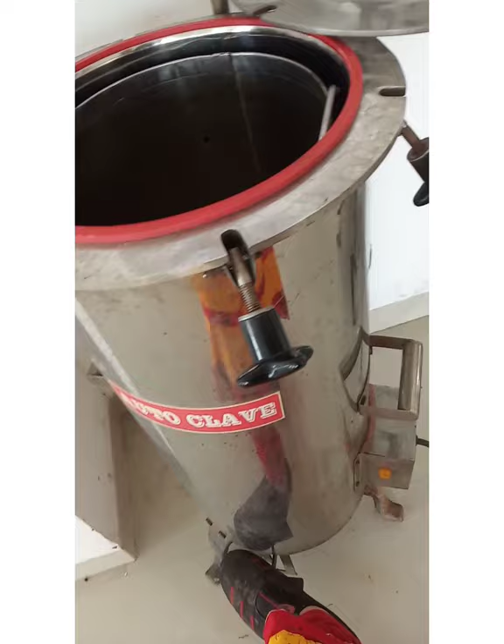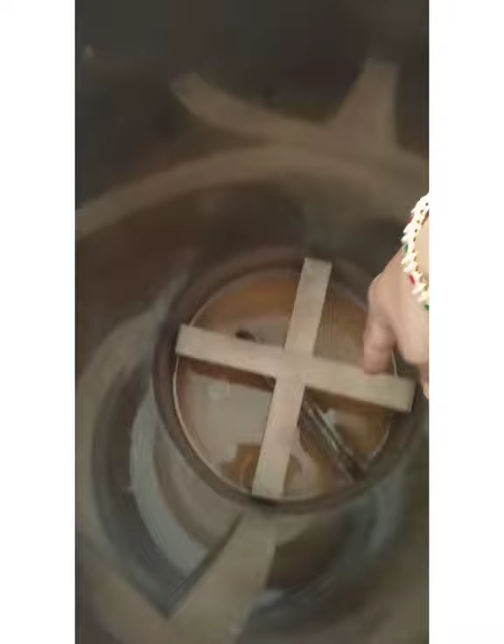So I told you there is a basket inside it. See, this is the basket. I will take it out. See, there is a heating coil present inside. Below this there is a heating coil, and we have to check the water level inside it properly. If the water level is correct, up to this mark, then you can place the basket in it and start the preheating of the autoclave. So I will keep this basket inside it, and now I will preheat it.